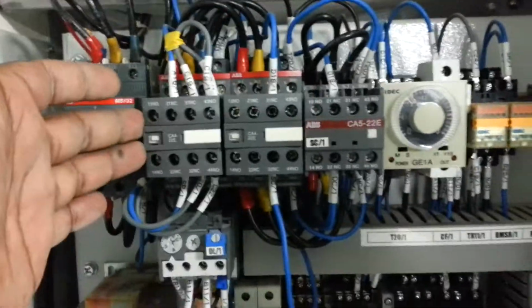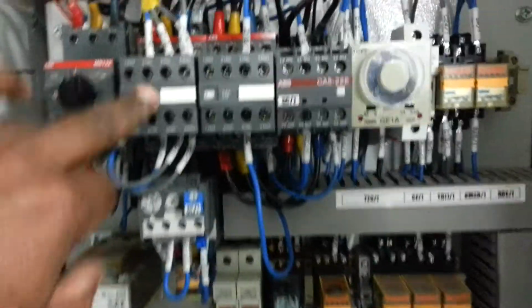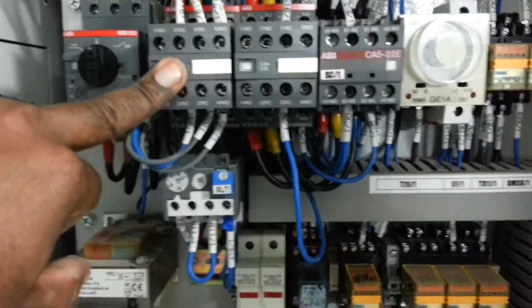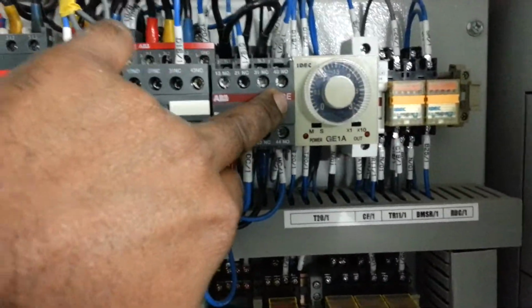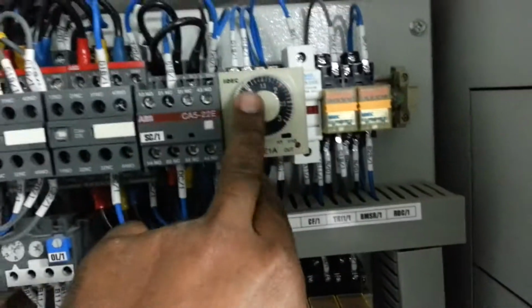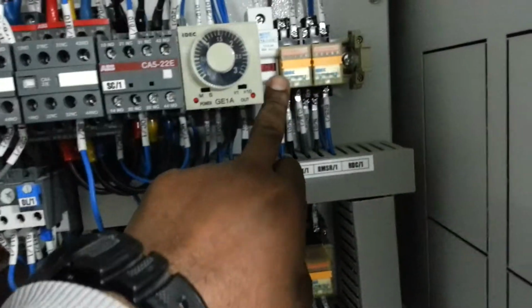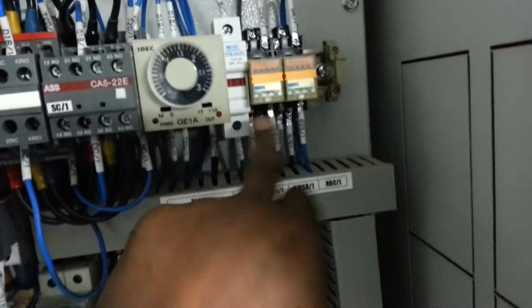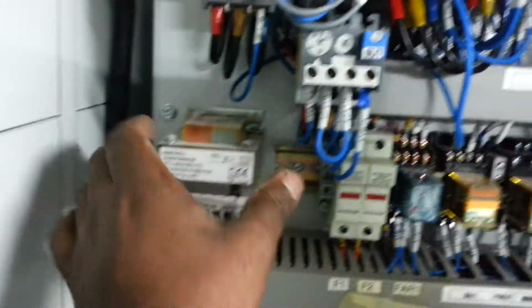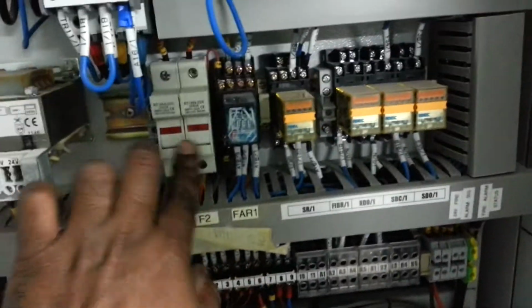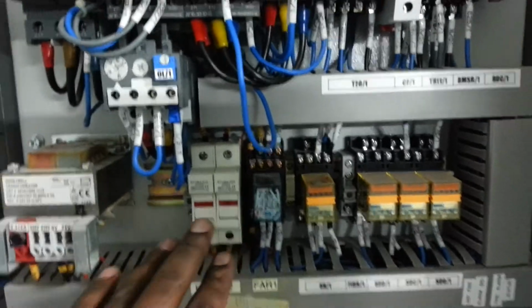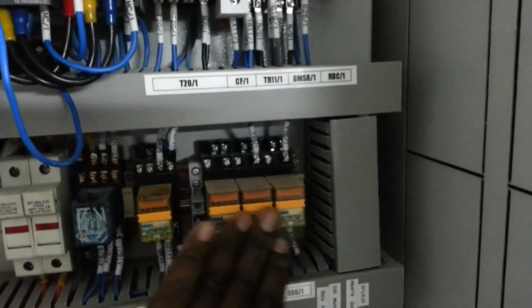And this is the star delta contactor. This is the main contactor, and this is the star, and this is delta. This is the timer, and here there is a control fuse, or this is the control supply. This is the control transformer. And here there is another fuse. This is for BMS and for fire. All these relays are related to the BMS and the fire safety relay.